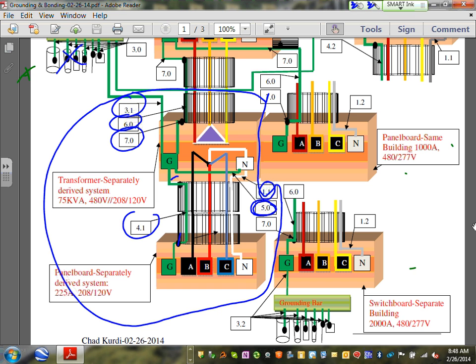From one end, they tie it inside the conduit, then they tie it with a grounding bushing. They tie it to one end inside the switchgear, the other end inside the transformer, and the other end inside the panel. So you have grounding bushings inside the panels. The way they do them, they bring the wire, they don't cut it, they loop it. They put it under a lug, tighten it, go through the conduit, then when they enter the second enclosure, they put it under another lug, tighten it to bond the conduit, and all the way to the ground bar inside the panel. Any comments, guys?